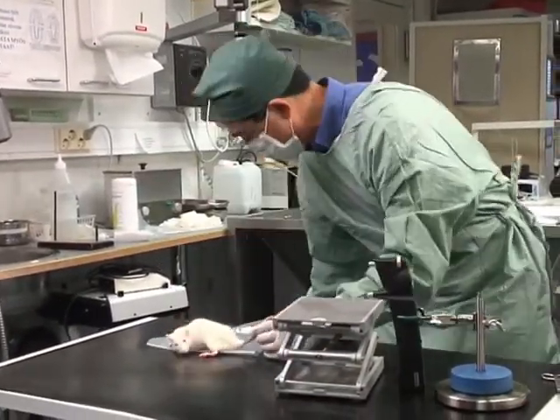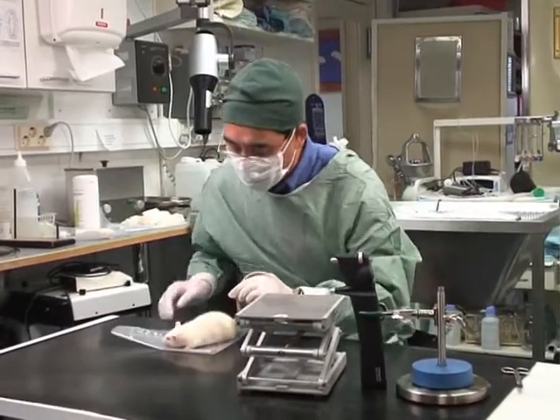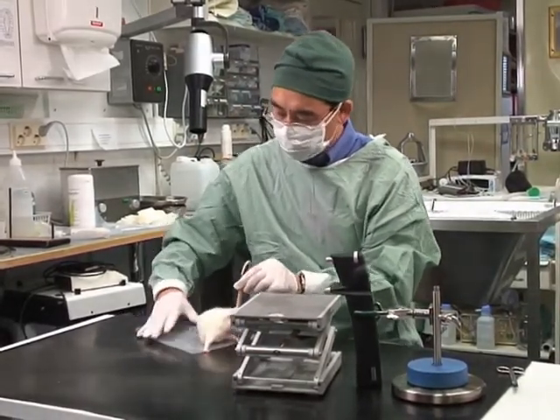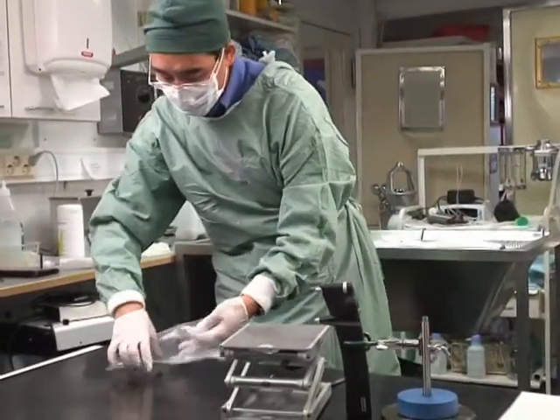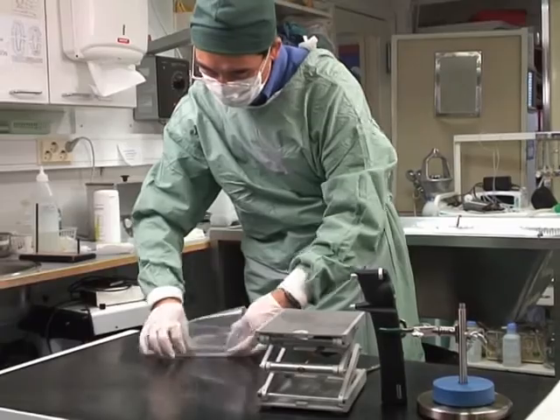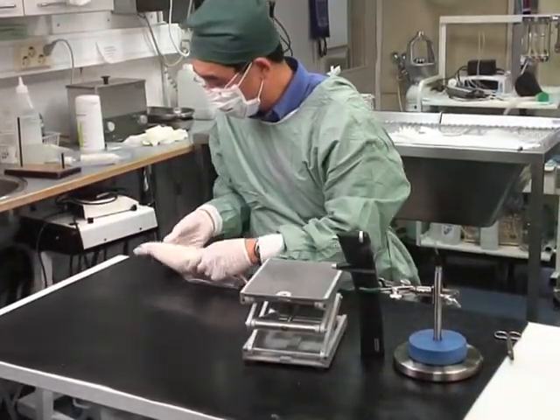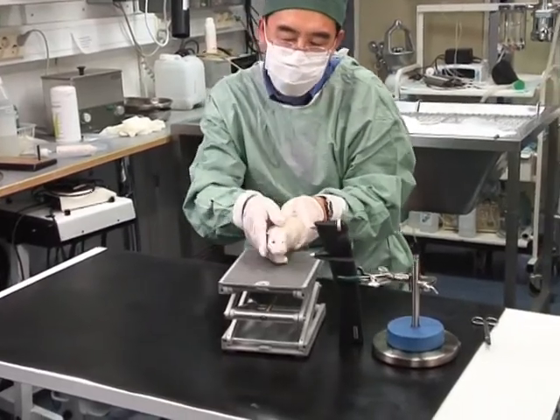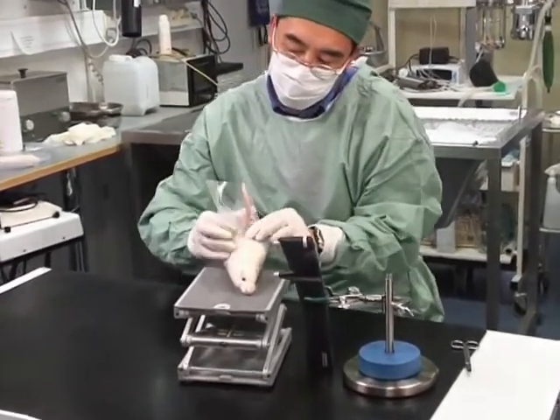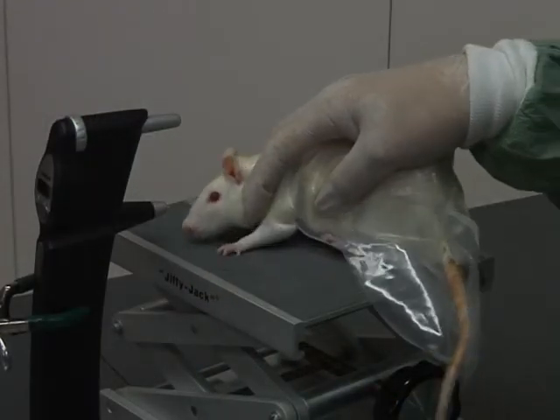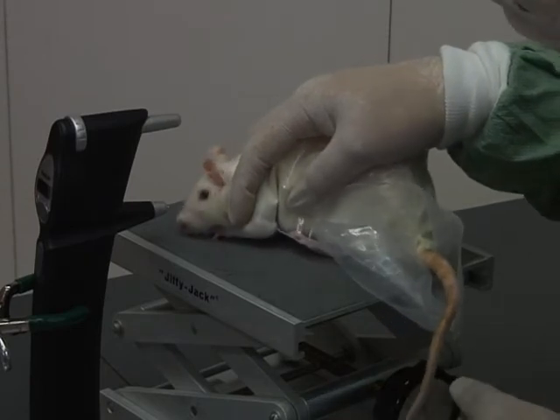IOP measurement in the rat. For the rat, a similar procedure is used. However, because of the larger body size, there's no need to use the restrainer for the IOP measurement. However, the rat may be placed into an unacclimated plastic decapicone for the IOP measurement. Set the TonoLab in rat calibration table by following the instruction. Cut whiskers with scissors if they block the probe's access to the eye.